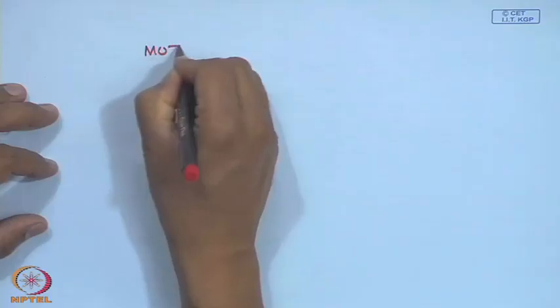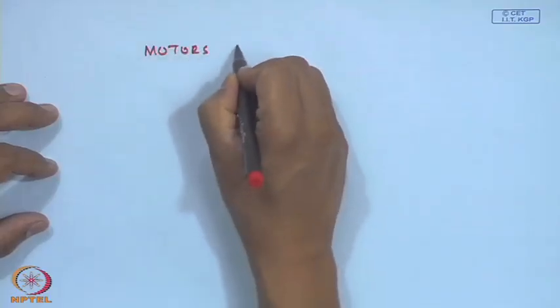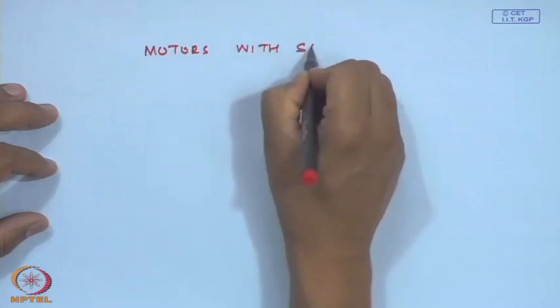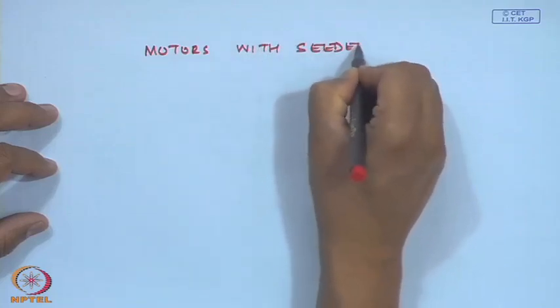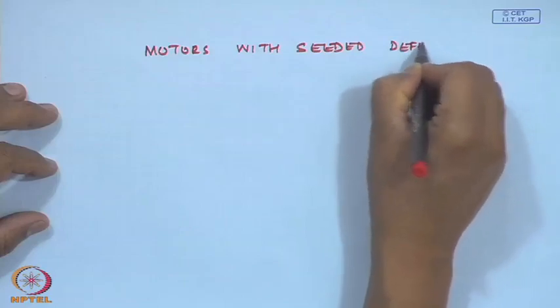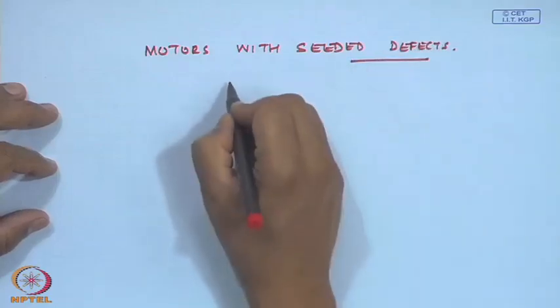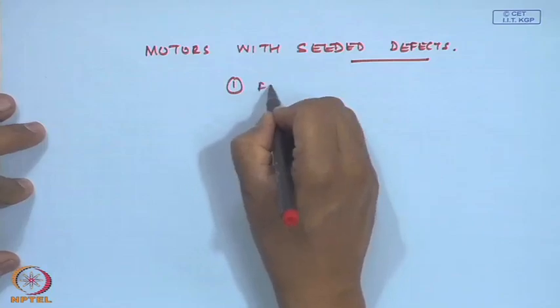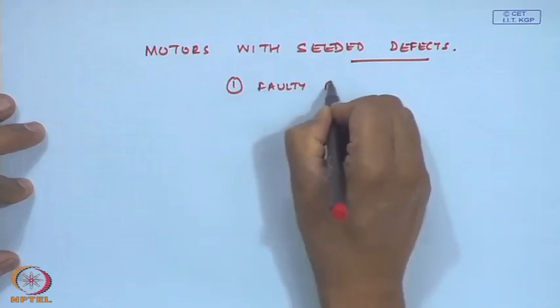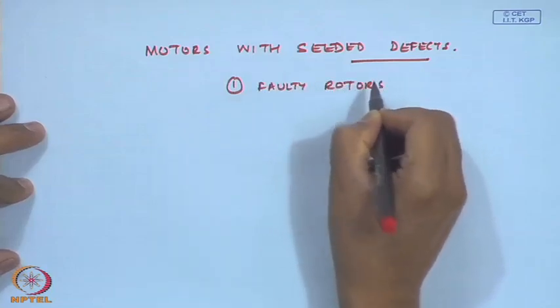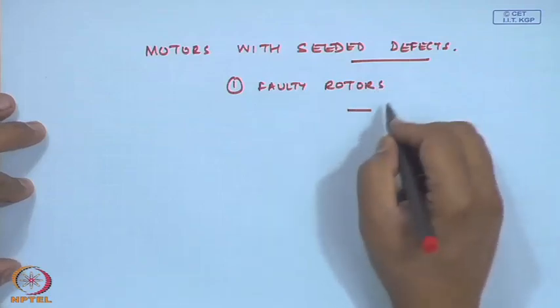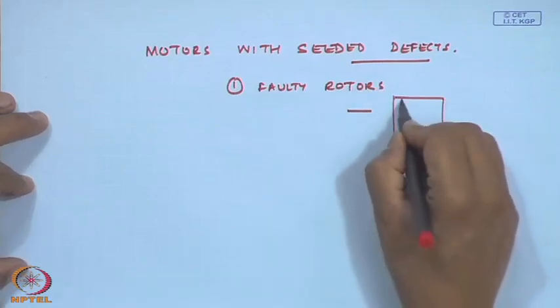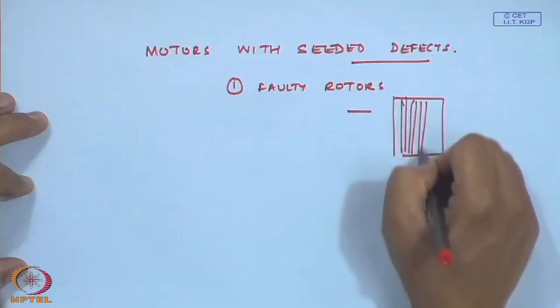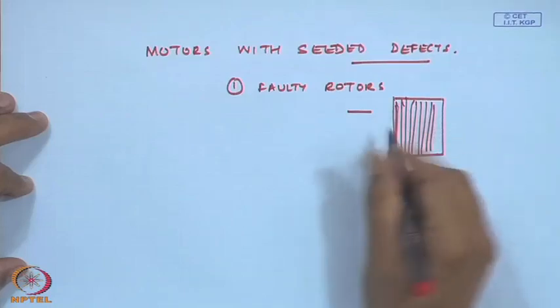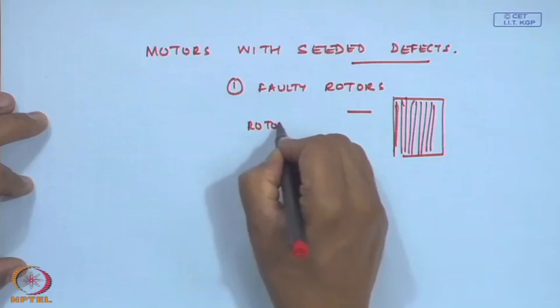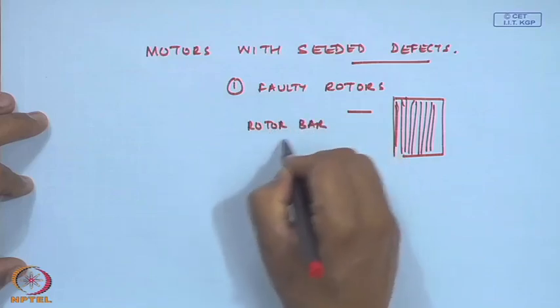So, we have motors with seeded defects. Okay, by seeded defects I mean there could be faulty rotors. Typically, faulty rotors means, you know, you have seen those rotor conductors like this in slots. Okay, so rotor bar broken is a common mechanical fault.